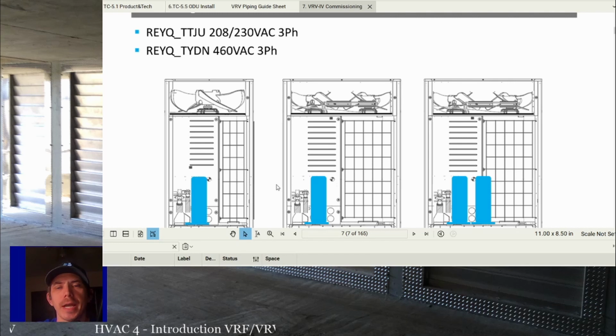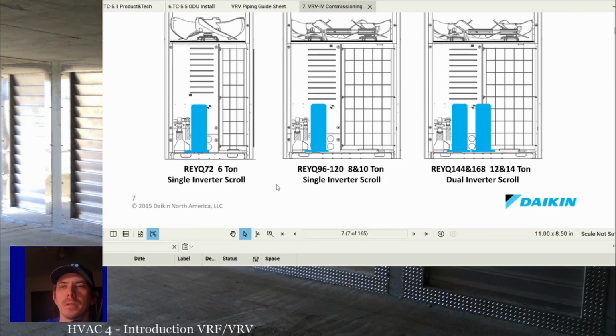The low pressure gas or suction line is the biggest line, and then the discharge or high pressure gas slash suction or low pressure gas is the medium size line. Sometimes those two lines are the same size, but if one is bigger than the other, the bigger one is your true suction, basically. All right.